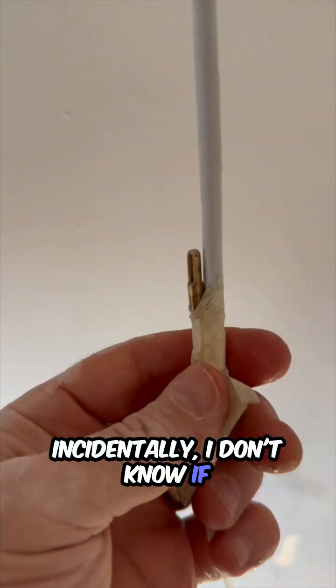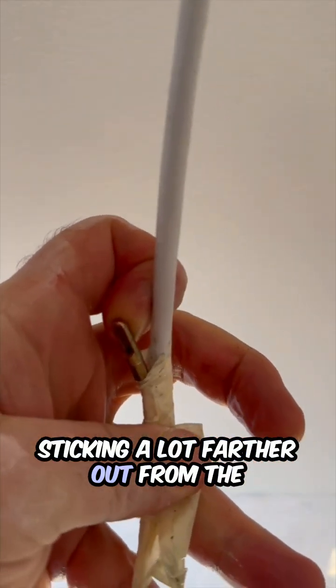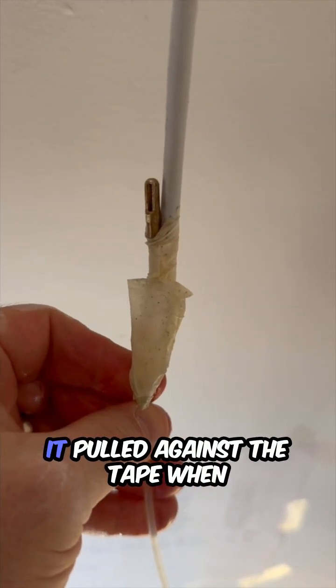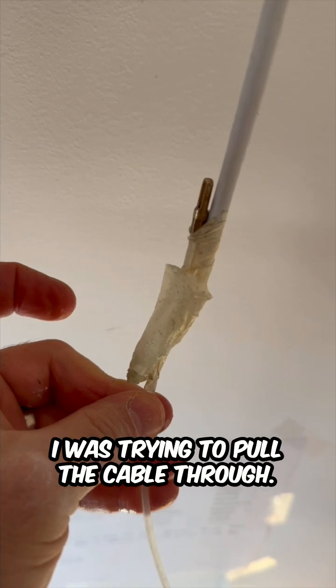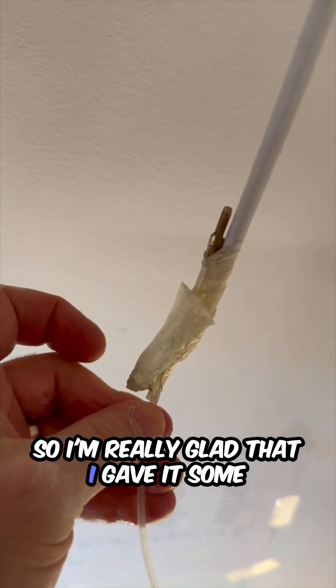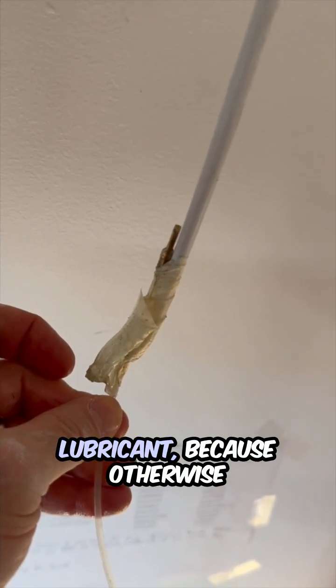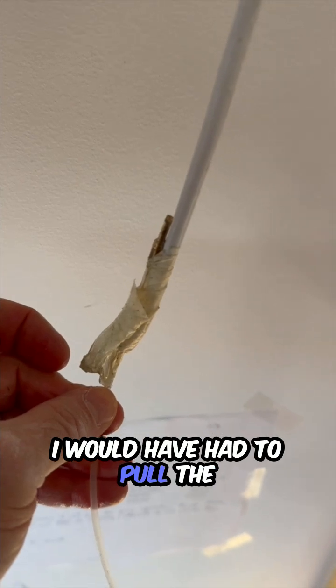Incidentally, I don't know if you remember, but this trailing end was sticking a lot farther out from the tape when I first taped it together. You can see how much it pulled against the tape when I was trying to pull the cable through. I'm really glad that I gave it some extra slack there and then backed out to try it with the lubricant, because otherwise I would have had to pull the cable puller out one side and the cable out the other and start all over.